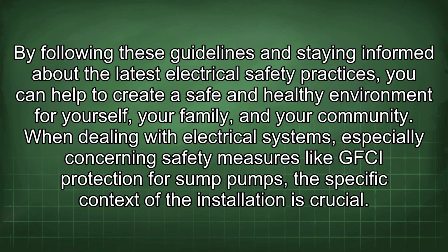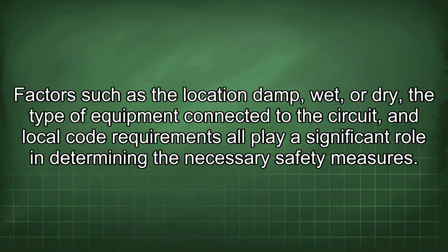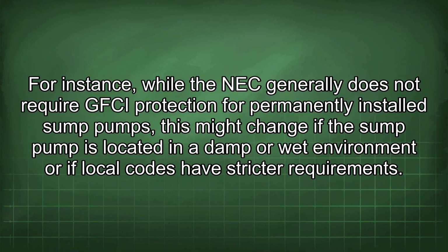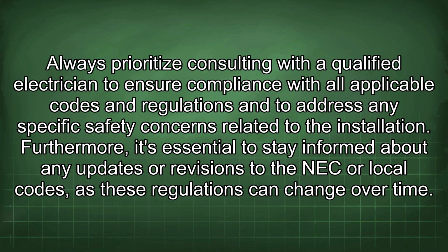When dealing with electrical systems, especially concerning safety measures like GFCI protection for sump pumps, the specific context of the installation is crucial. Factors such as the location, damp, wet, or dry, the type of equipment connected to the circuit, and local code requirements all play a significant role in determining the necessary safety measures. For instance, while the NEC generally does not require GFCI protection for permanently installed sump pumps, this might change if the sump pump is located in a damp or wet environment or if local codes have stricter requirements. Always prioritize consulting with a qualified electrician to ensure compliance with all applicable codes and regulations and to address any specific safety concerns related to the installation.